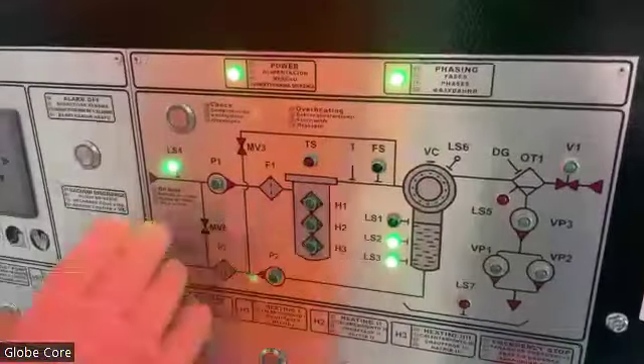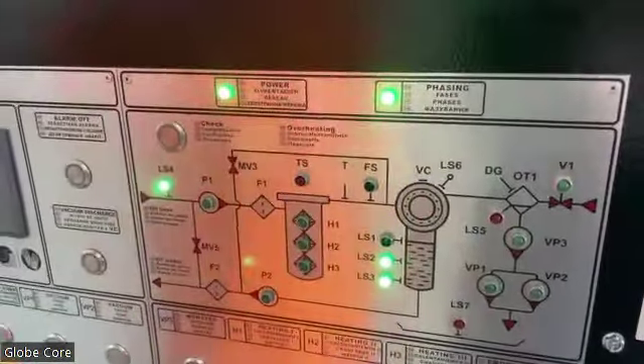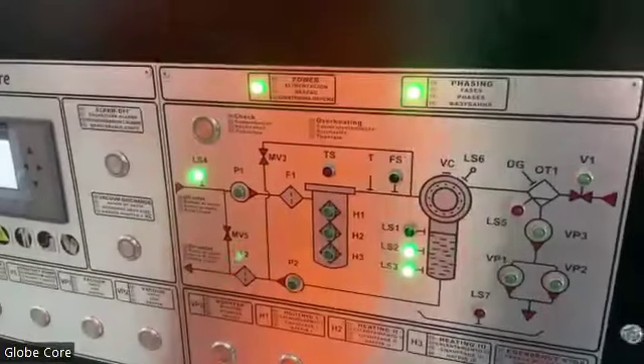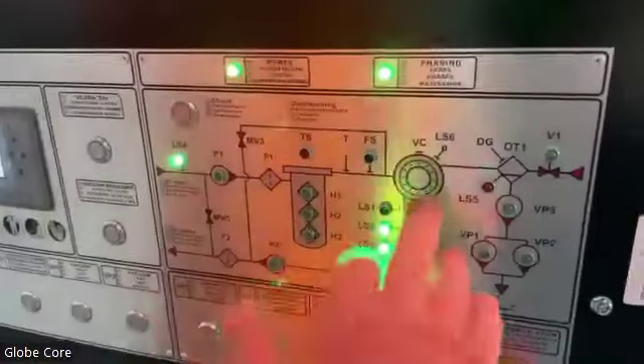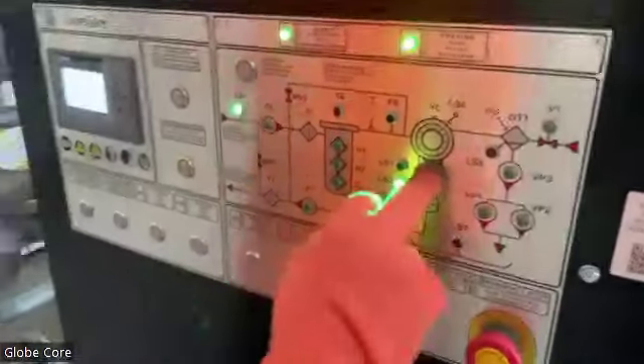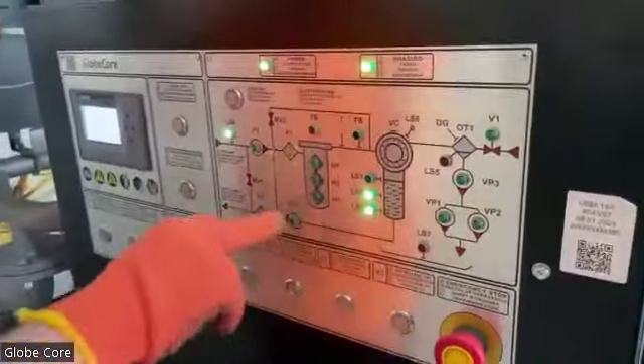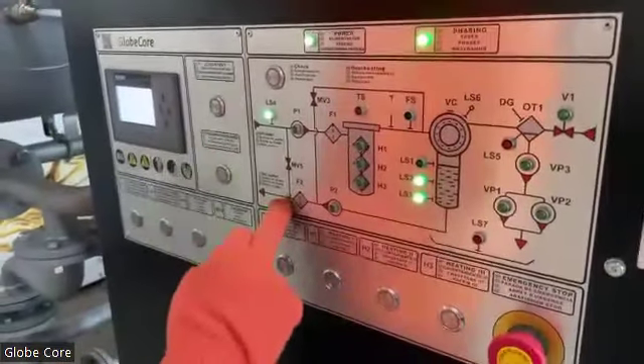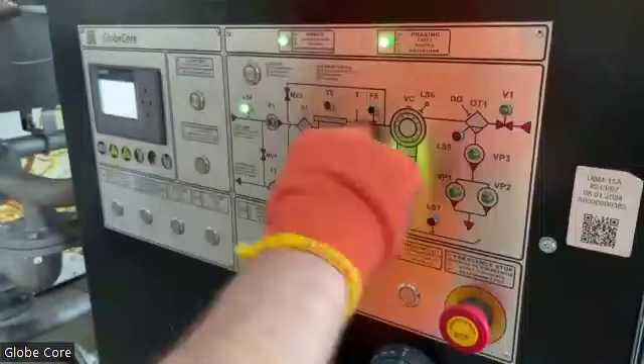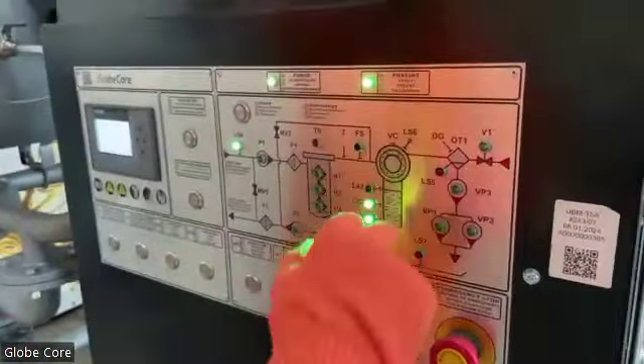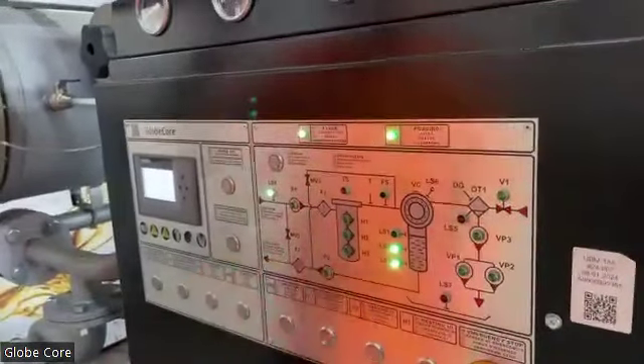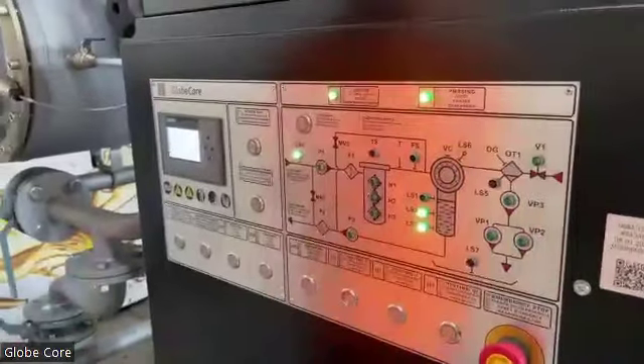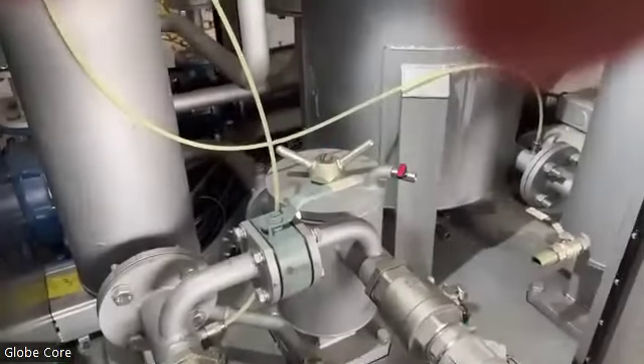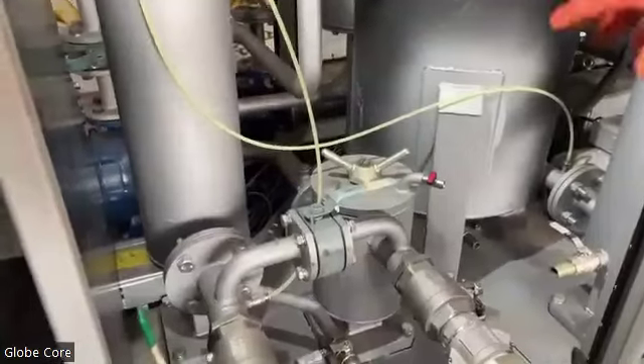This is quite important because this is part of the starting procedure of the unit. After the first filling of the unit, we warm up the unit by circulating oil from the vacuum chamber by the outlet pump through the bypass valve, through the inlet pump, through the filter, through the heater, back into the vacuum chamber. So this internal circulation allows us to warm up the unit and to prepare the first portion of oil. Now I want to show you this valve, MV5. It is over there. So we open it to arrange internal circulation inside the unit.